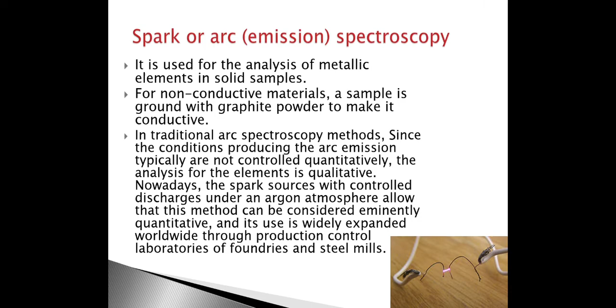Next is spark or arc emission spectroscopy. It is used for the analysis of metallic elements in solid samples. For non-conductive materials, a sample is ground with graphite powder to make it conductive. While in traditional arc spectroscopy the method was purely qualitative, now, due to advanced technologies, the spark sources with controlled discharge under an argon atmosphere allow this method to be considered eminently quantitative, and it is widely used in the laboratories of foundries and steel mills.